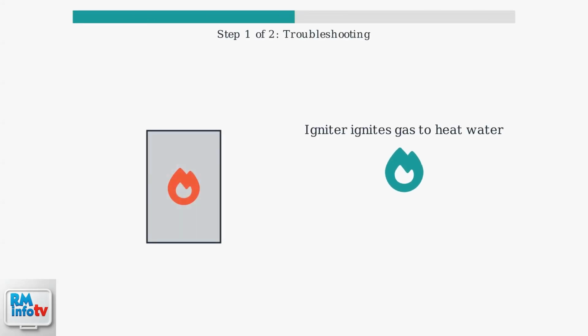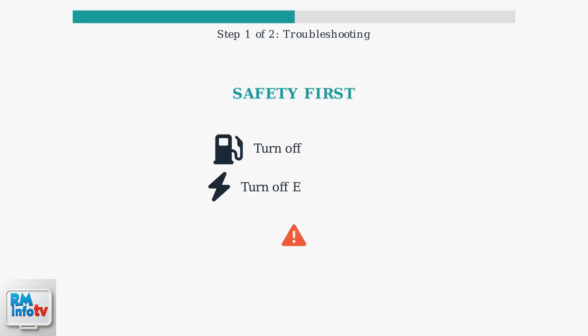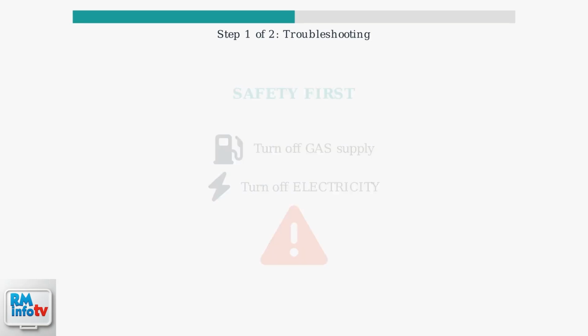When your State Select water heater fails to produce hot water, the igniter is often the culprit. The igniter is responsible for igniting the gas that heats your water. Safety is paramount when working with gas appliances. Before beginning any troubleshooting, you must turn off both the gas supply and electricity to the water heater unit.